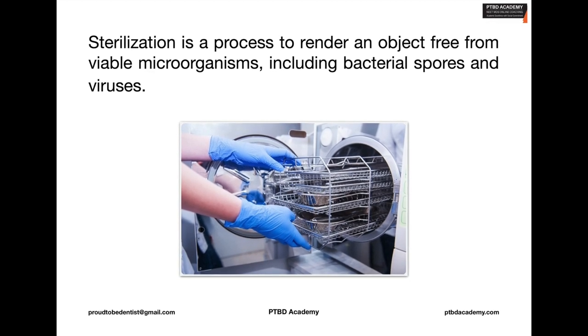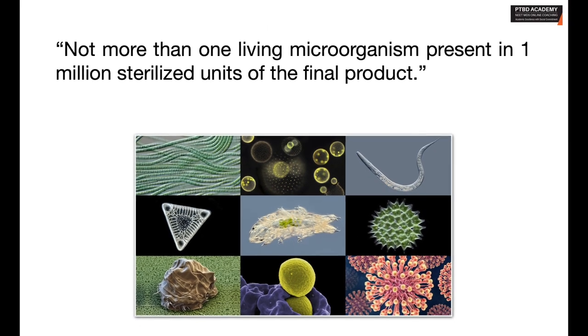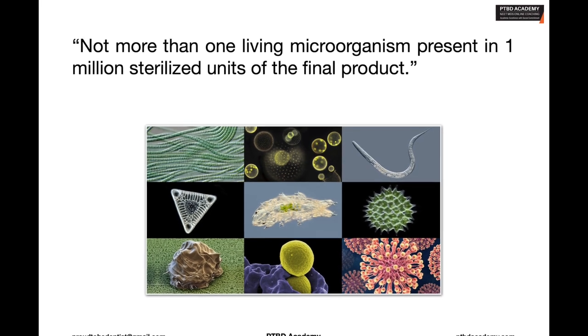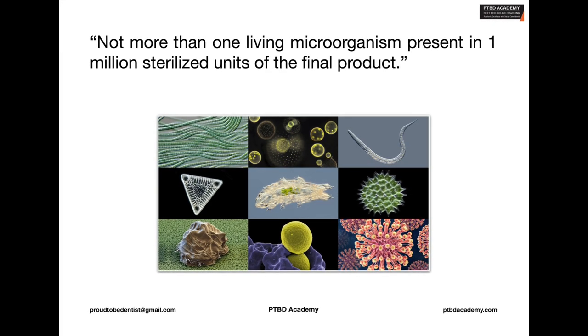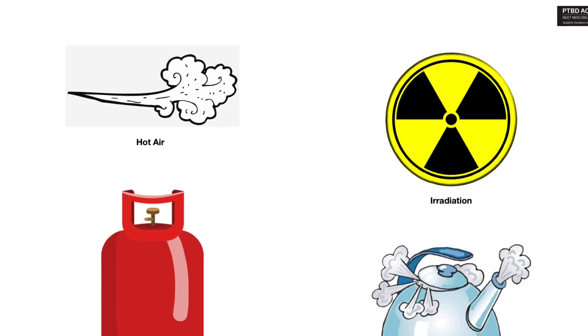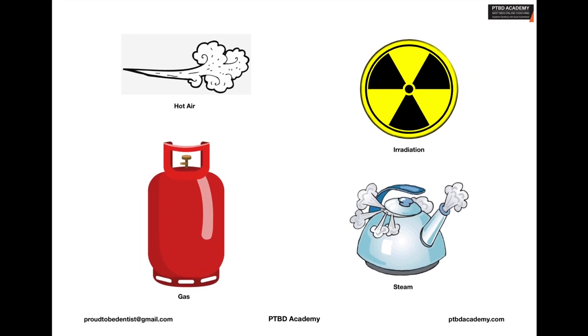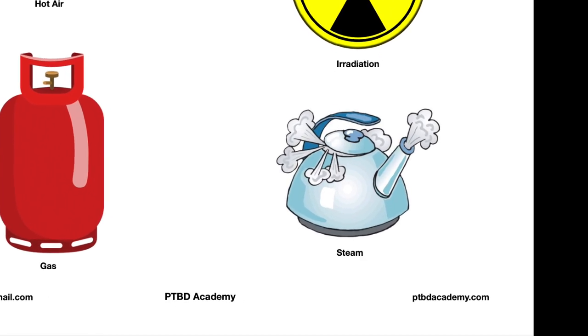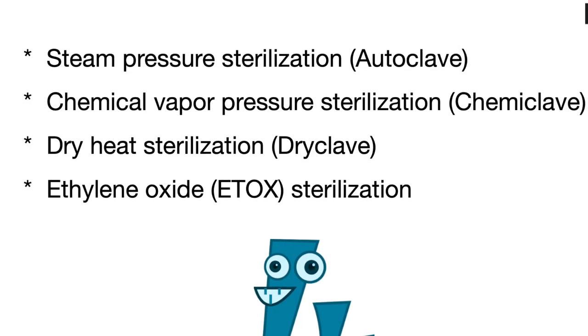It's an all-out war — we do not want any microbial factors when we're using instruments in patients. Sterilization can be theoretically described as not more than one living microorganism present in one million sterilized units of the final product. Items are required to attain this standard in order to achieve the term 'sterile.' This process can be achieved in a number of ways including hot air, gas, irradiation, and steam — and of all these methods, steam sterilization is most commonly used as it is quick, effective, and offers a simple yet reliable method.